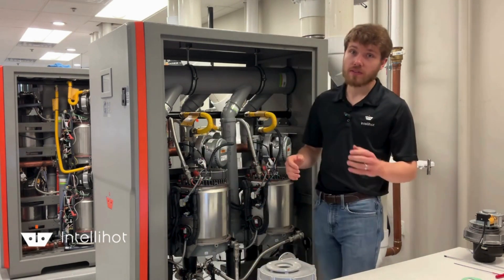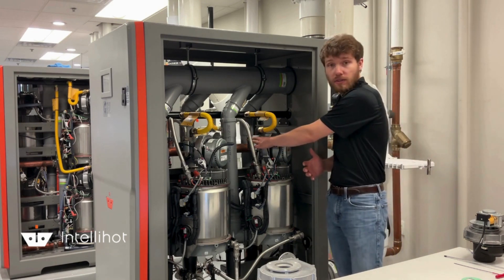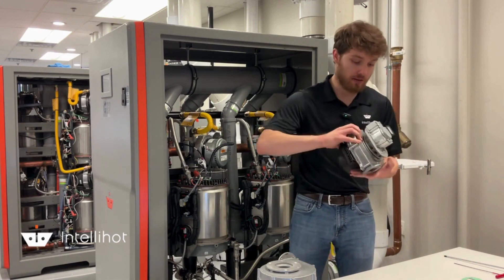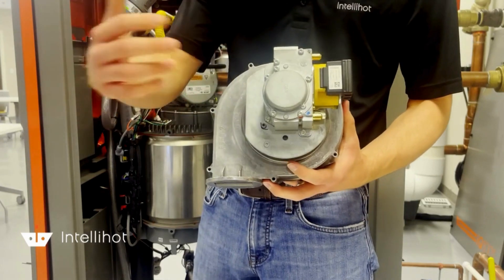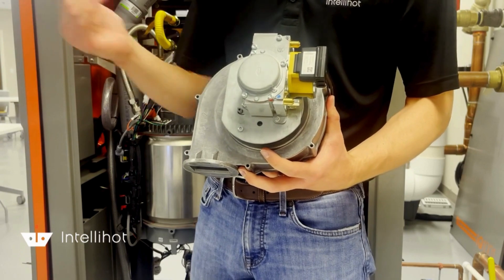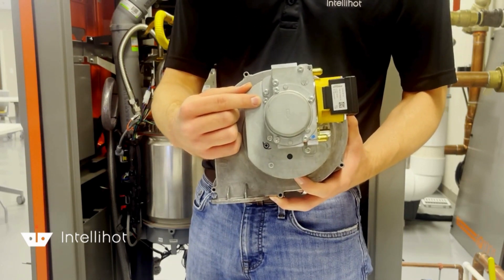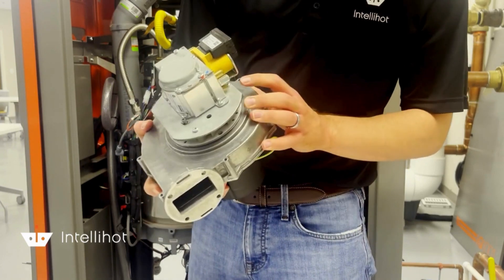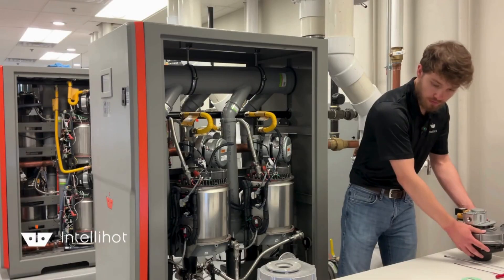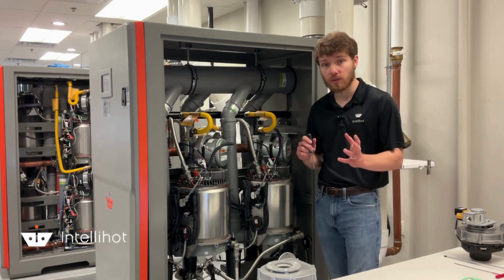First thing we're going to do is take off the blower that's already on the system. We actually have to take the gas valve off of the blower in order to start this process. It's a little bit hard to see in the unit, so I have a blower gas valve assembly here. On the back of the gas valve assembly there are three screws we're going to remove — they're the screws that go all the way through the swirl plate. I need a T20 screwdriver in order to do that.